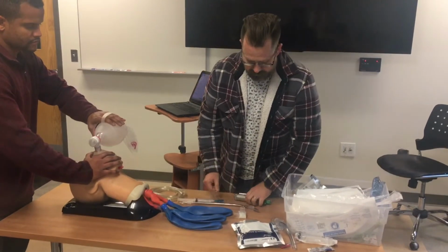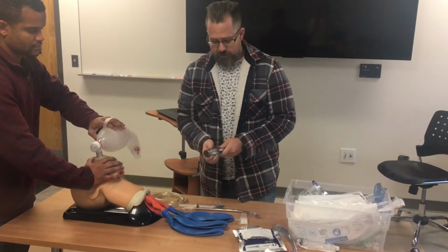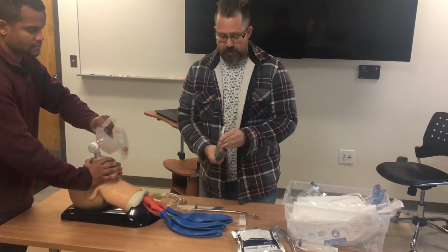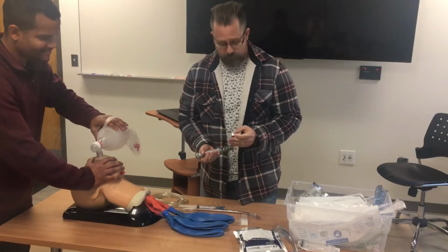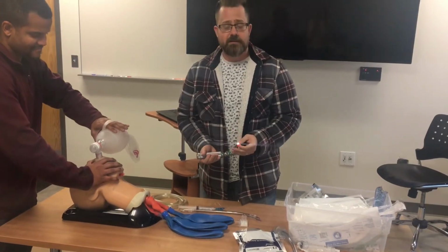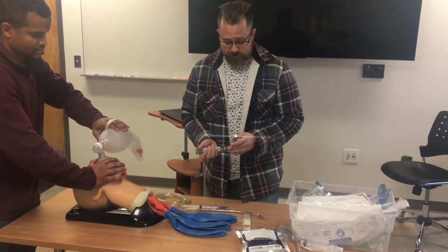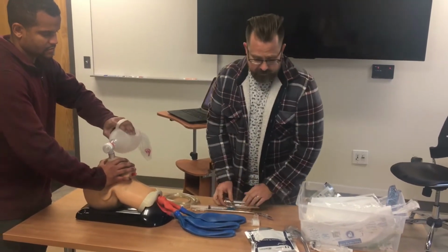And then you want to check your laryngoscope handle and blade. What you're looking for is light, tight, and bright. A lot of these blades have a little bulb on the end of it that rotates. You want to make sure that that is screwed down tightly, so that it doesn't fall off into the oral cavity. So we've got light, tight, and bright. This equipment is good.